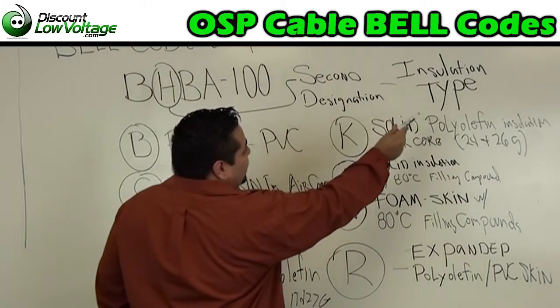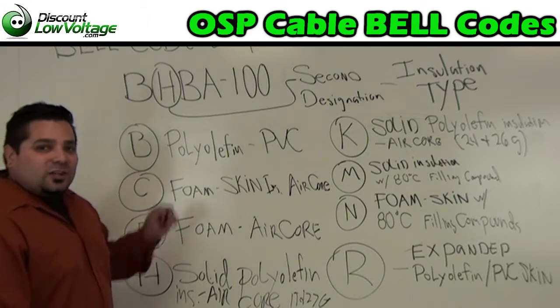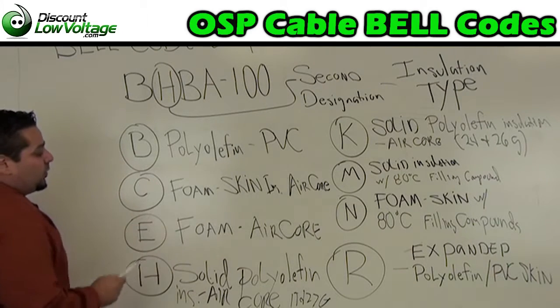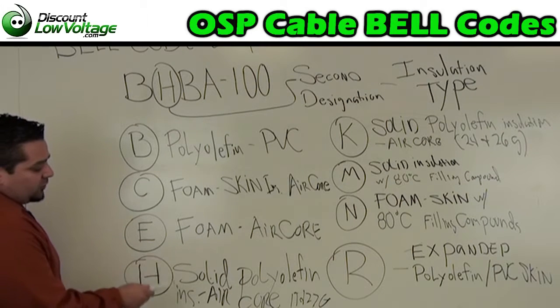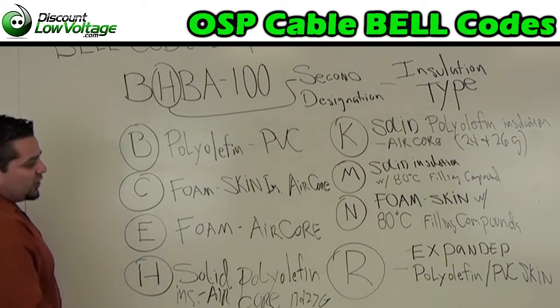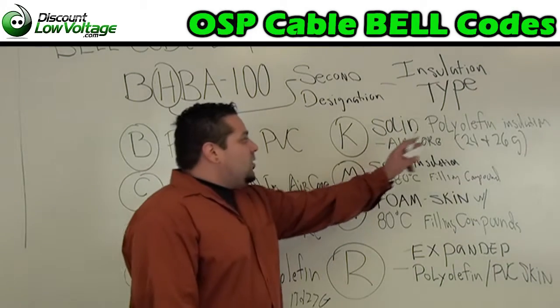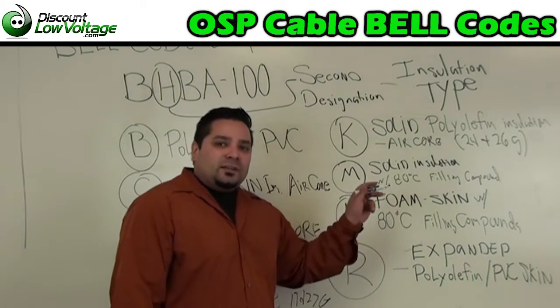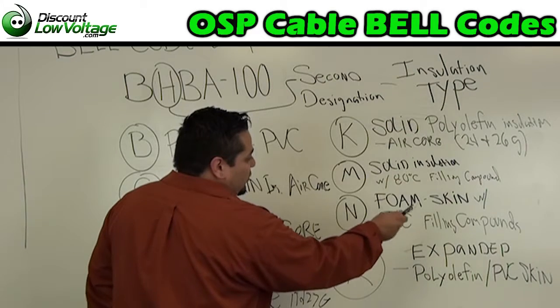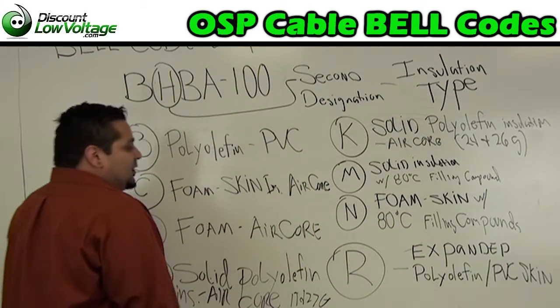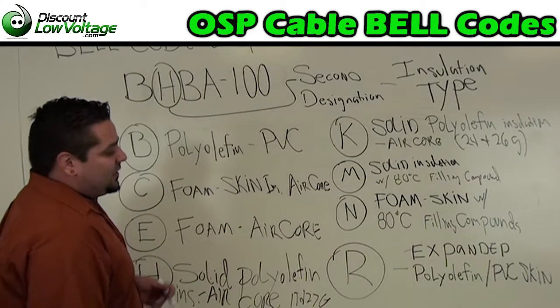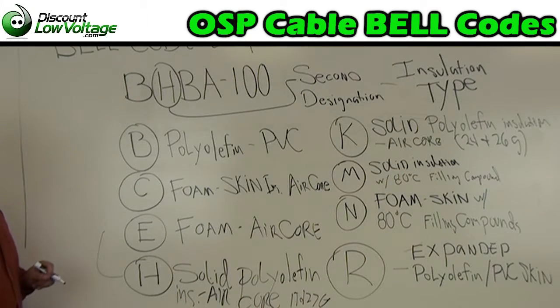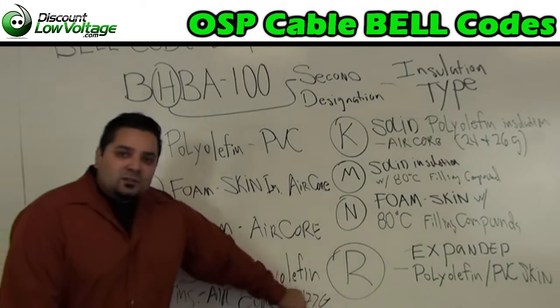For our second designation, it stands for the insulation type. B, poly PVC. C, foam skin insulation air core. E, foam air core. H, solid poly air core for 19 and 22 gauge cable. K, solid poly insulation air core for 24 and 26 gauge. M, solid insulation with an 80 degree Celsius filling compound. N, foam skin with an 80 degree Celsius filling compound. R, expanded poly PVC skin insulation. We have H, so we have a solid poly insulation air core, and this also tells us we have a 19 to 22 gauge cable.